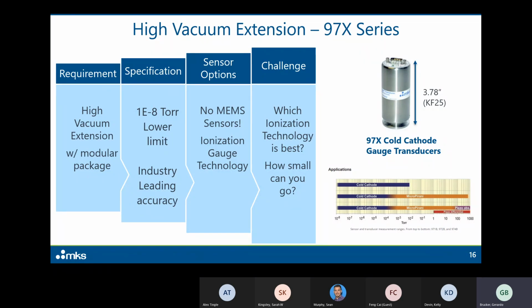So there were two things that we had to resolve very quickly. Which ionization technology is best, and how small can you go? Can we keep this small form factor and still provide you with an accuracy-leading ionization gauge for your analytical instrumentation? Well, the bottom line is I'm giving you the answer already. Yes, we were able to do this. We developed a 97X cold cathode gauge transducers family, which can cover all the way from 10⁻⁸ to atmosphere in a single sensor or multi-sensor configuration, including a version that includes load lock handling capabilities.